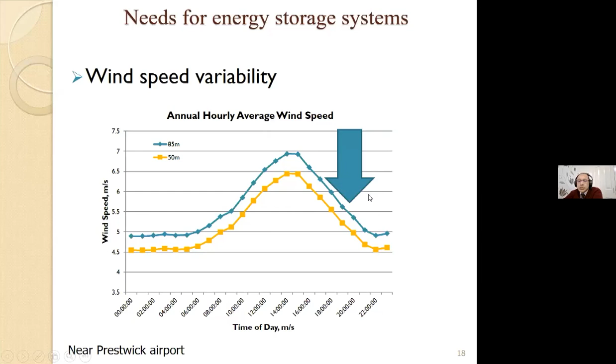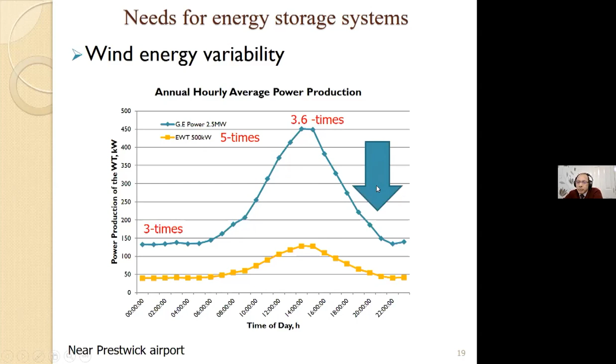The issue is during peak load time, the wind energy produced is less, so we're not getting the most benefit of the installed capacity if you want to match the load. If we increase the scale of the wind turbines from 0.5 megawatts to, say, 2.5 megawatts, 5 times larger, you will never produce 5 times the energy. Just increasing the size of the wind turbine is good, you'll produce more, but not as much as you think. As you can see here, the maximum for a 5 times rating is only 3.6 times the maximum energy that can be produced.